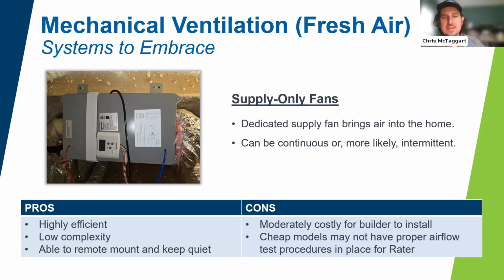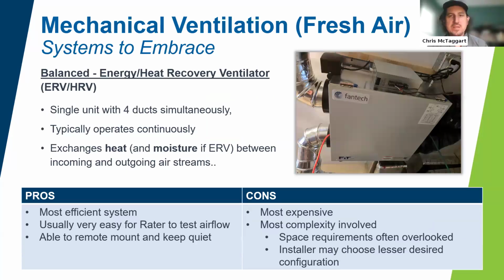I'd say the other con is that in certain temperature conditions, you may be blowing in either very cold air or very hot and humid air. And so the feeling of that can be more palpable potentially for the customer. The solution to that is to put in a balanced heat recovery or energy recovery ventilation system. The benefit of it is that it recovers some of the heat from our house, so that if it's really cold outside, we're pre-tempering that air so it doesn't feel so uncomfortable. These are also very energy efficient because they're capturing that heat flow, and there can be some very good ones that are relatively low electrical energy use.